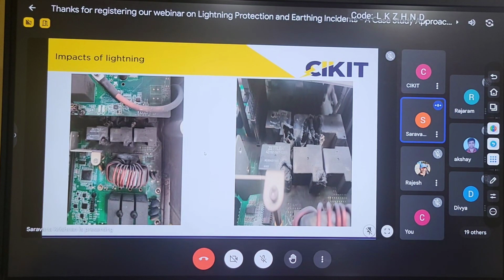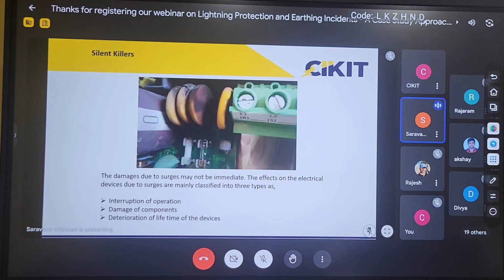The damages caused by surges are mainly classified into three types. One is interruption of operation, the second is damage of components, and the third is deterioration of lifetime. Interruption of operation means the equipment gets turned off, and if I turn it on again, it will work normally. The second one is damage of components, and the image shown is related to that. The third one is deterioration of lifetime. If the magnitude of the surge is much lower, then even though damage is not caused, the lifetime of the component may get reduced.